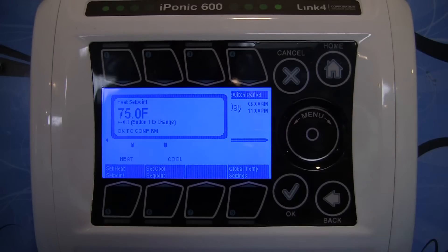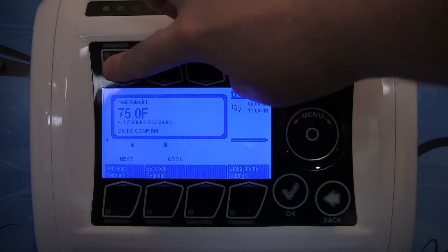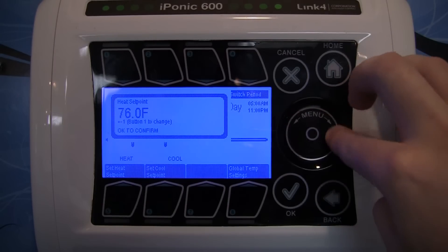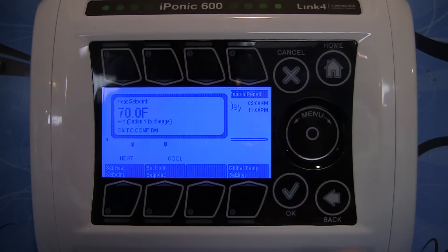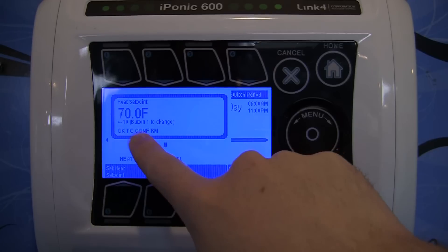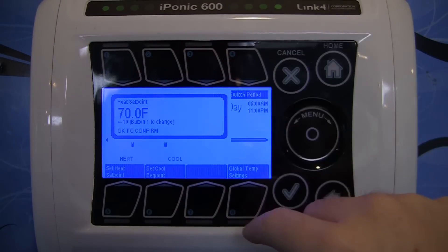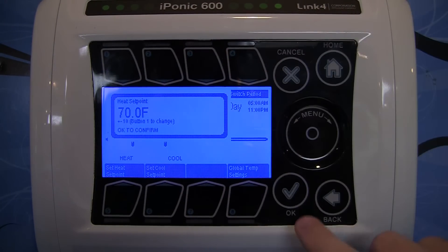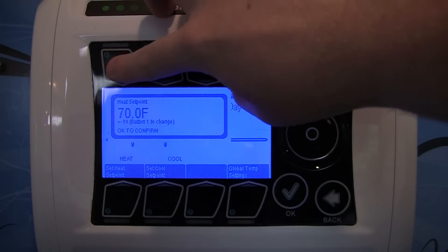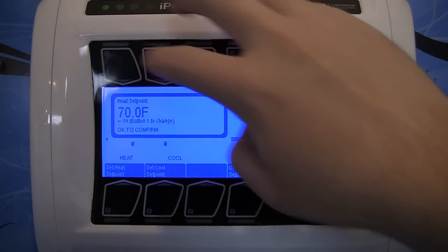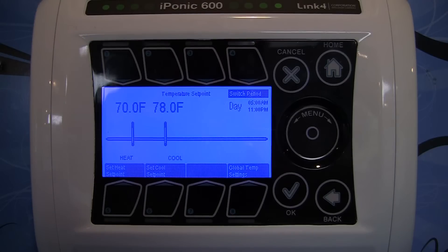If you want to move by a larger increment, hit button number one and you'll move in increments of one degree. Pressing it again moves to 10-degree increments, so you can quickly move from 60 to 50 and back up to 70. Pressing button one cycles through 0.1 degree, 1 degree, and 10 degrees. I'll set the heat set point to 70 and hit OK.